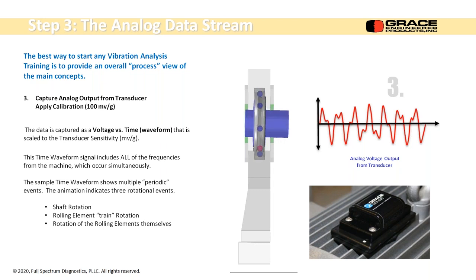The transducer's picking them all up in a raw voltage versus time signal. We apply transducer sensitivity, typically 100 millivolts per G, and now it's a time waveform in acceleration. Because the accelerometer will pick up acceleration. We can mathematically change that like we talked about a moment ago, but we don't have to do that right now. So there's the shaft rotation, the train rotation or the cage of the bearing, and then the rotation of the rolling elements themselves.